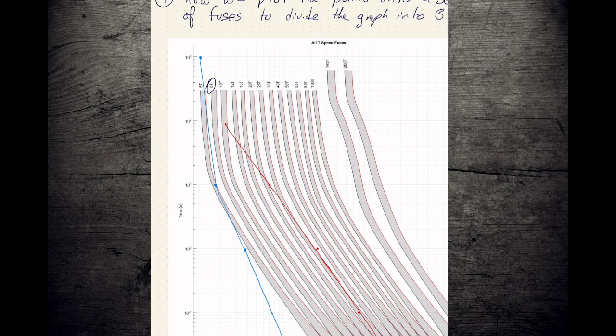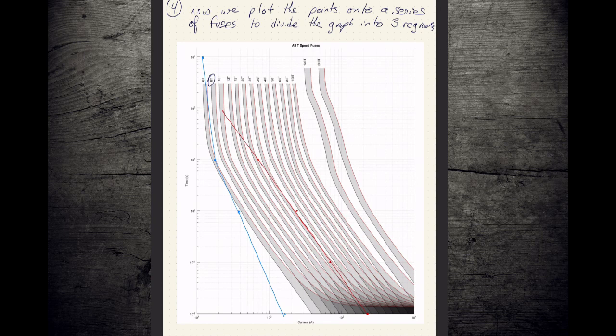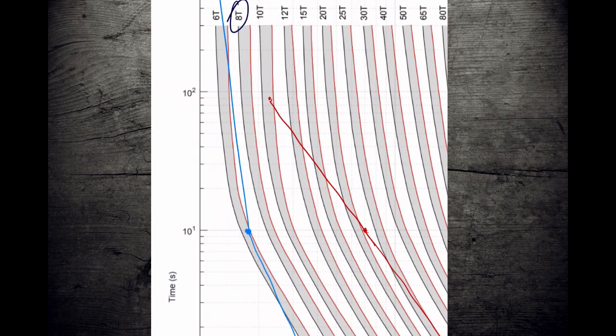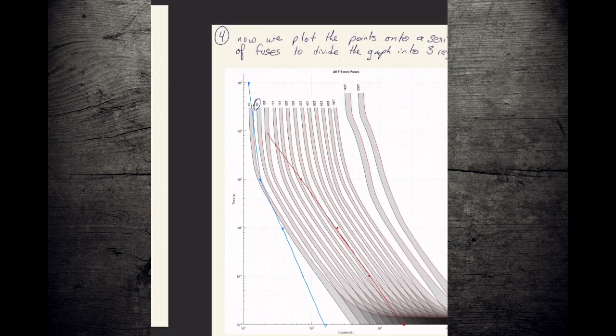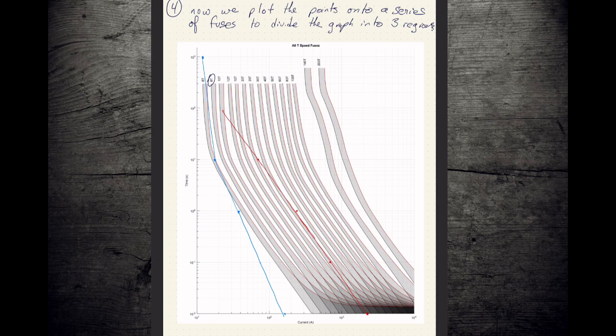You take a look at something like the 12T fuse, and we can see that the 12T fuse spends most of its time in the sweet spot between the two fuses, but up here, around 20, 30, 40, around 50 seconds, well, actually closer to 40 seconds, you get into this spot where the transformer could be damaged and the fuse doesn't operate. So again, not ideal. For this little stub here, for these conditions here, if you ever get into the big overload, the high impedance fault where you don't have a really good connection, but you still got too much current flowing, you could cook this transformer and the 12T fuse would be happy to just sit there and not do anything about it. The 8T fuse, on the other hand, is perfect. It sits entirely in between those two lines in our protection margin from top to bottom. And so for this transformer, the 8T fuse would be the perfect one.